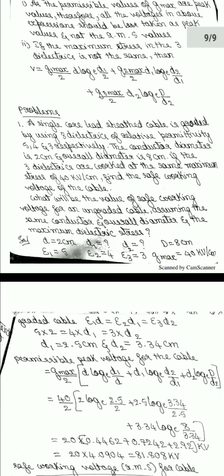d is equal to 2 cm, they have given d1 is not given, d2 is also a question mark, capital D is 8 cm, epsilon 1 is 5, epsilon 2 is 4, epsilon 3 is 3, G maximum is equal to 40 kV per centimeter. Graded cable means epsilon 1 into d is equal to epsilon 2 into d1 is equal to epsilon 3 into d2. From that you find out d1 and d2, because we know the value of small d, so we can find out the small d1 and d2.